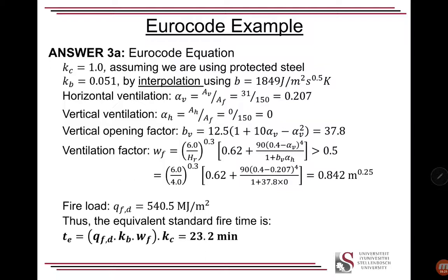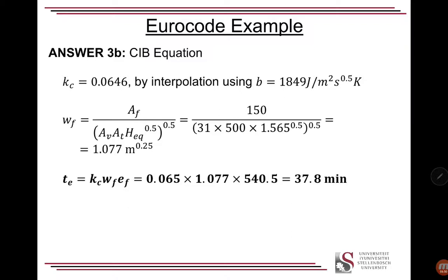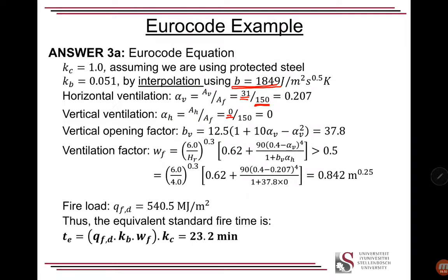So now, coming to the equation, this is the answer to the question above, to determine the equivalent fuel load. So kc is 1, so we're assuming using protected steel. If we were using something different, we'd possibly have to adjust this if it was unprotected steel. And then our kb, so this is Eurocode from the value above, I've interpolated it using a thermal inertia of that, and that was calculated in the previous video. Horizontal factors we've got 31 square meters over 150 square meters of floor area. I'm sorry, just going back. And then we've got no roof vents, a vertical opening factor, and calculating vent areas because it's a four meter high boundary. And we have a ventilation factor. Fire load as previously calculated, plugging it in, and we get to a time of 23 minutes.